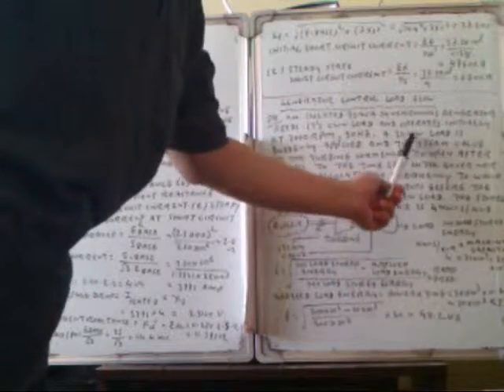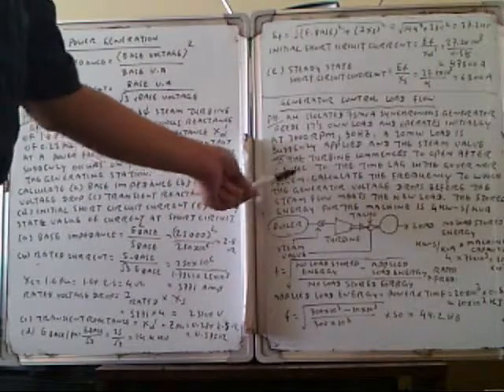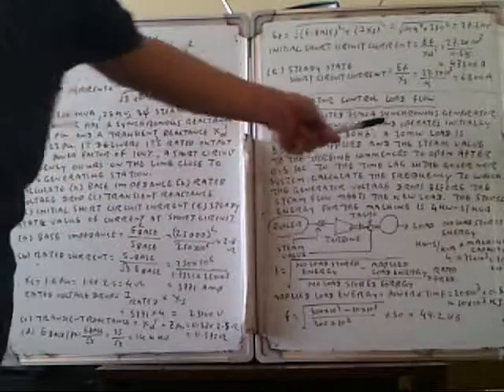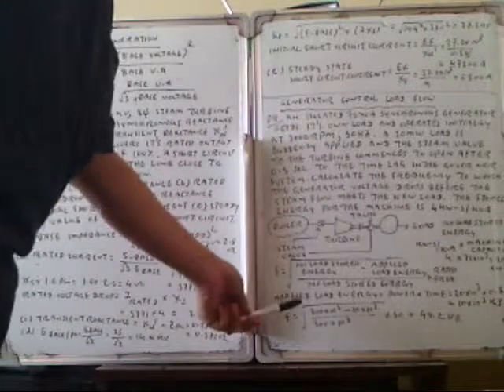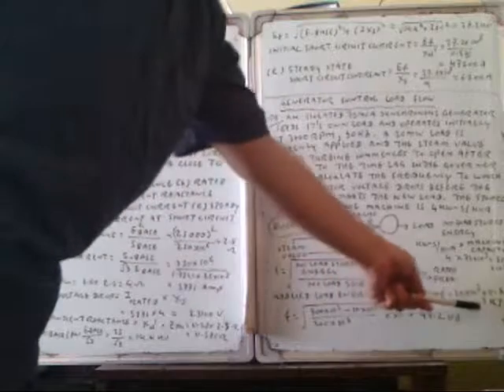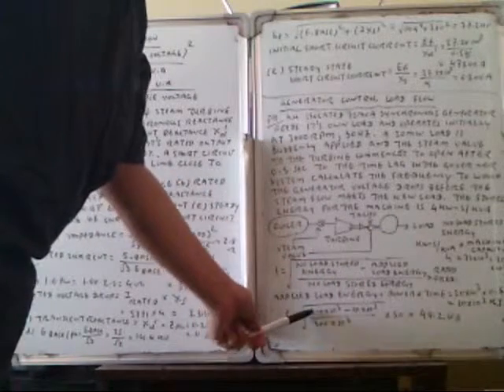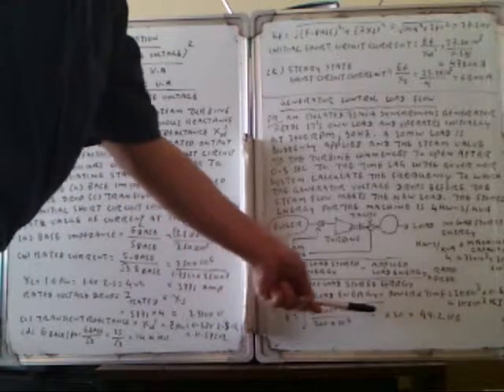The applied energy is the applied load power multiplied by time. The load is 20 MW = 20 × 10³ kW, applied for 0.5 seconds, giving applied energy = 20 × 10³ × 0.5 = 10 × 10³ kW·s. Substituting into the formula: square root of (300 × 10³ − 10 × 10³) / (300 × 10³), multiplied by 50, gives approximately 49.2 Hz.